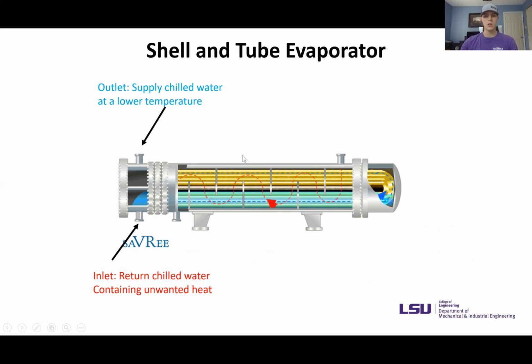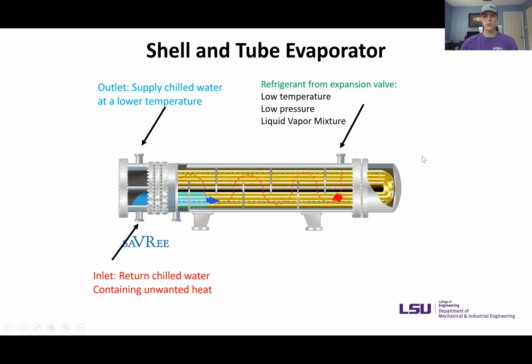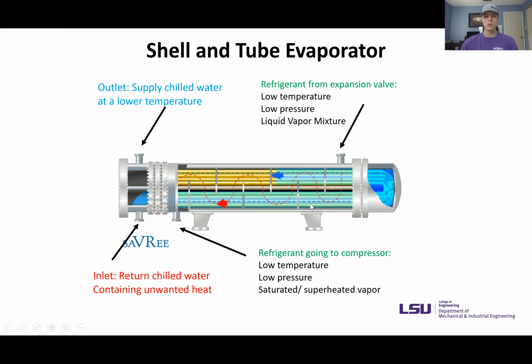a lower temperature. And the reason it's at a lower temperature is because the refrigerant from the expansion valve at a low temperature, low pressure liquid vapor mixture passes through the evaporator and picks up that unwanted heat from the chilled water, and then the refrigerant will exit as a low temperature, low pressure, saturated or superheated vapor.